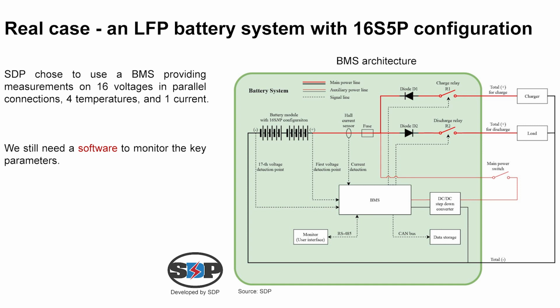The battery system can be charged by the charger. The charge current passes through the charge relay, R1, the diode, D1, and the fuse. If something goes wrong during charge, the charge relay will be turned off immediately by the BMS. The D1 diode guarantees that the current cannot feed back to the charger, avoiding damage to the charger by the feedback current. On the other hand, the battery system still can discharge to the load.